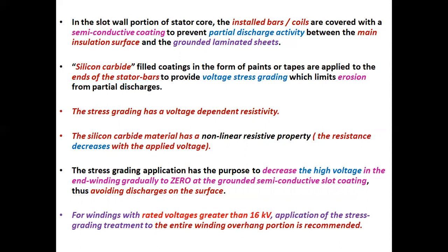That is, the resistance decreases with the applied voltage. The stress grading application has the purpose of decreasing the high voltage in the end winding gradually to zero at the grounded semiconductive slot coating, thus avoiding discharges on the surface. For windings with rated voltages greater than 16 kV, application of the stress grading treatment to the entire winding overhang portion is recommended.